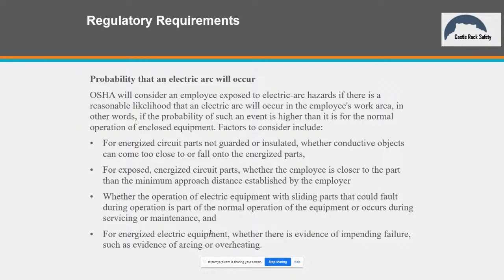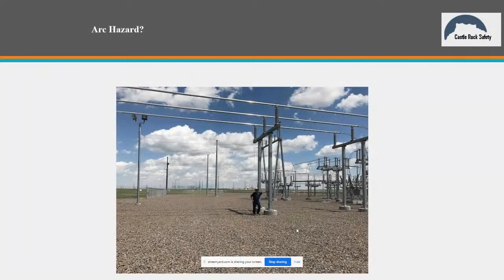So as you read these regs, what you're finding is that it's pretty clear that OSHA is looking at work, right? It's no different than on the utilization side, guys. If you're not working on stuff, if you're not interacting with the equipment, there's no arc flash hazard, right? Yep. But gosh, I'm seeing stuff out there that's just driving me nuts. My good friend Clint here is standing out in a substation, right? 20 feet, 25 feet below a substation bus, wandering around this yard, in no way is he exposed to an arc flash hazard, right? And the rules don't apply to that unless, of course, I'm working, doing something that could cause that arc flash.